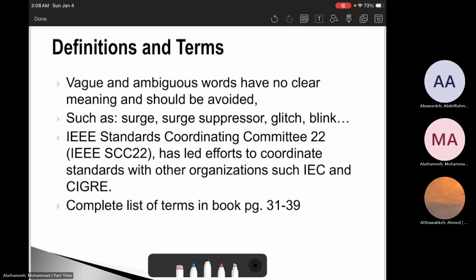So, the other thing, which is the types of problems: we don't use vague words. Warning words like surge, glitch, and blink sound helpful, but they are not engineering terms. If a customer says surge, it could mean a transient, a swell, a sag, a momentary interruption, or even a harmonic problem. Power quality monitoring requires precise language because the solution depends on the event type. As an example, if the event is a sag, a surge protector will do almost nothing. If the event is a transient, then the surge protector matters in a lightning strike. If the issue is harmonics, then the surge protector does nothing and you need a filter or load redesign.